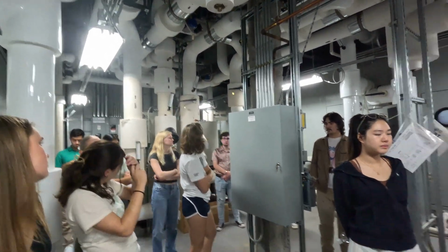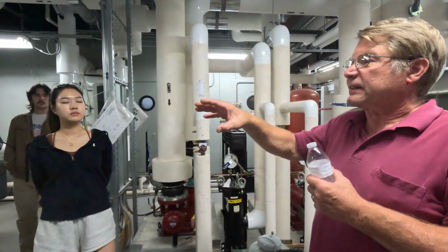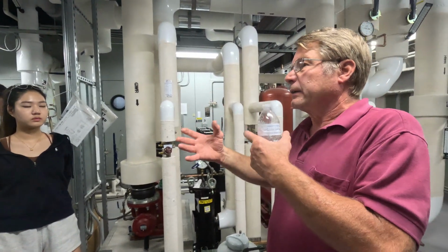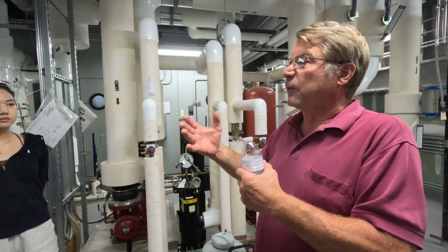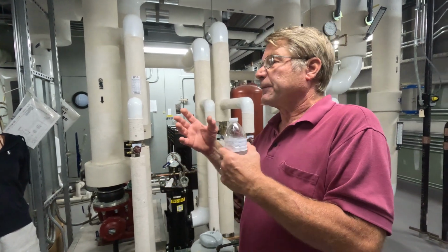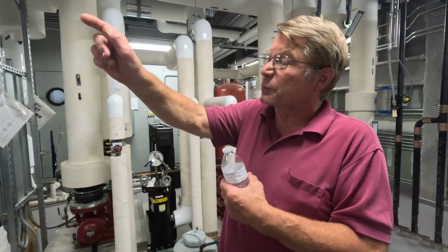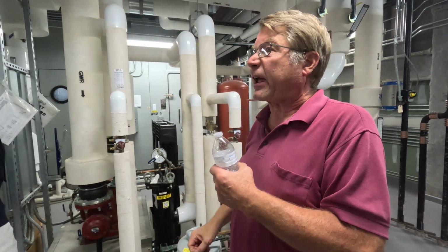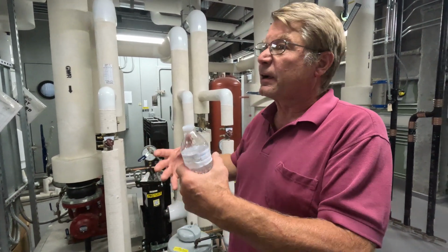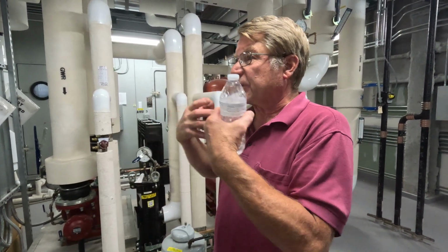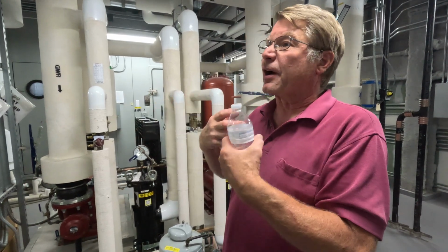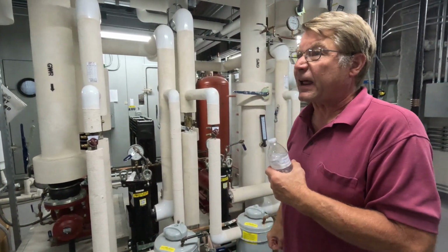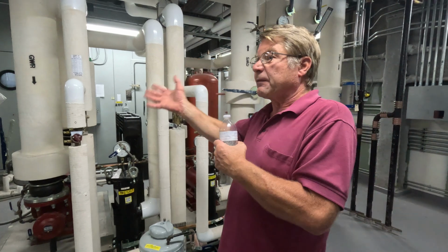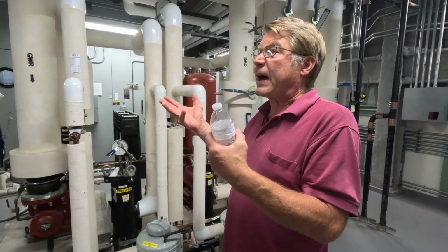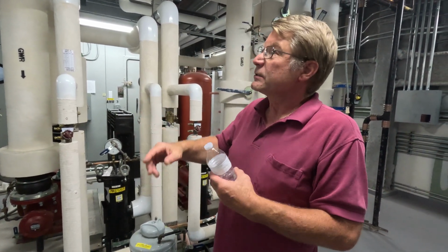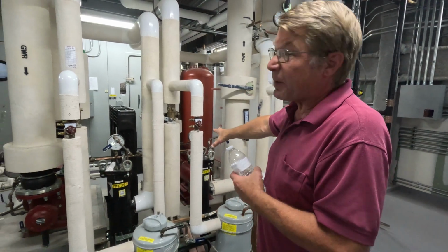In the summertime then, that multi-stack chiller will take that 72-degree water and then cool it down to about 45 degrees, okay? That 45-degree water will go to those reclaim coils at the beginning of the air handling unit that I was showing you earlier to pre-temperature, preheat there, pre-cool the air coming in to start tempering that air. So when you take 72 degrees and cool it down to 45, you got to get rid of the heat somehow. So then that water then comes over to these pumps here.